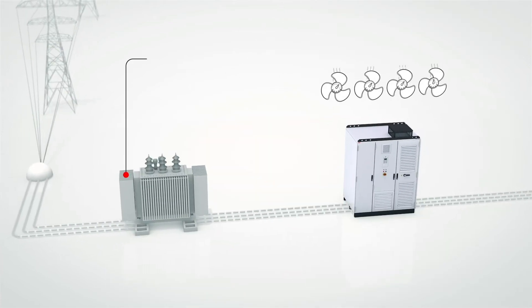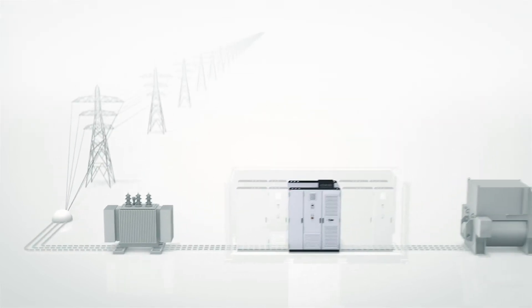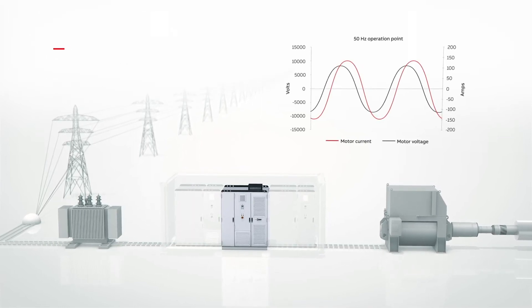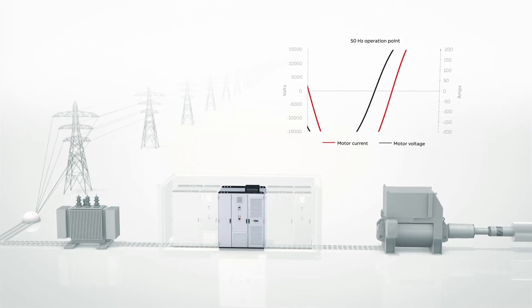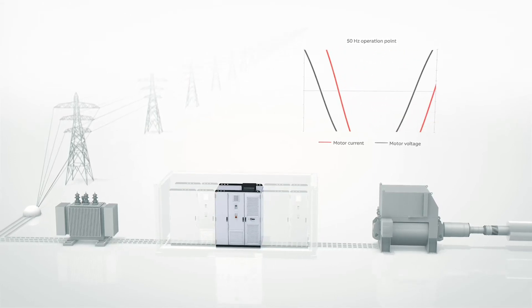The transformer can also be placed outside, minimising the heat losses and space requirements in the e-house. Maximum motor compatibility makes the drive suitable for standard motors of all ages. A sine filter is optionally available for a perfect output power quality. The result is an excellent waveform of voltage and current supplied to the motor.